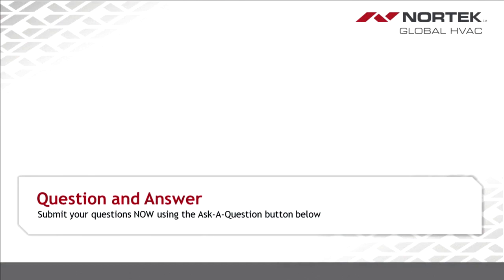So the first one here, Greg, is: what if the indoor unit has a Y1 and a Y2, and the outdoor unit only has a Y terminal? Which terminal should be used inside? Okay, Dana, that's a great question. If you've got a Y1 and a Y2 on the indoor unit but only a Y outside, that would be a situation where you have a Nortek unit that's actually a two-stage capable inside unit. And when we say two-stage capable inside, we're talking about the blower having two-stage capability, basically a lower cooling speed and a higher cooling speed. But if your outdoor unit only has one Y connection, it's just single stage.